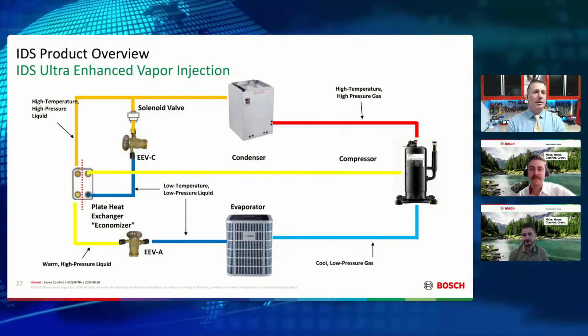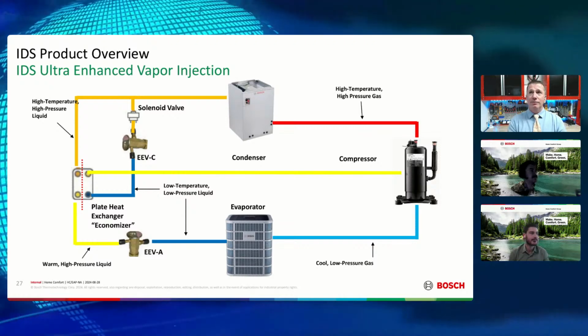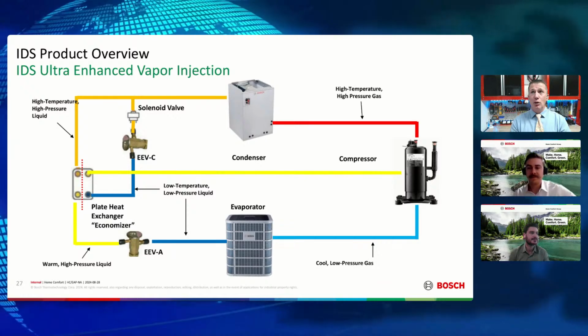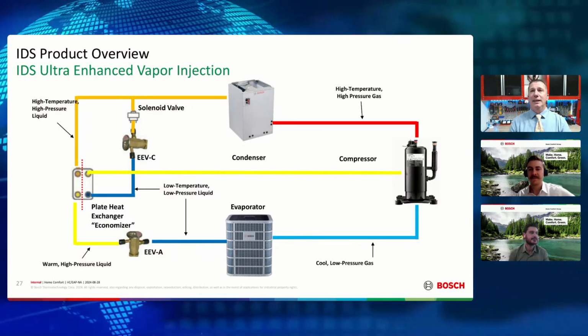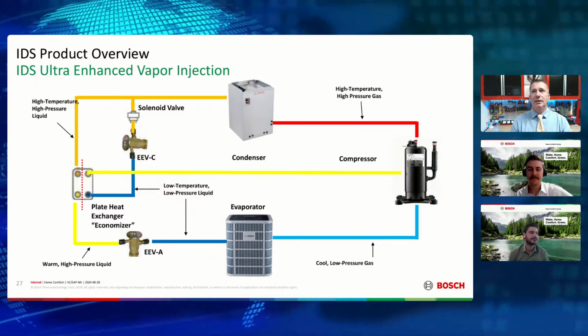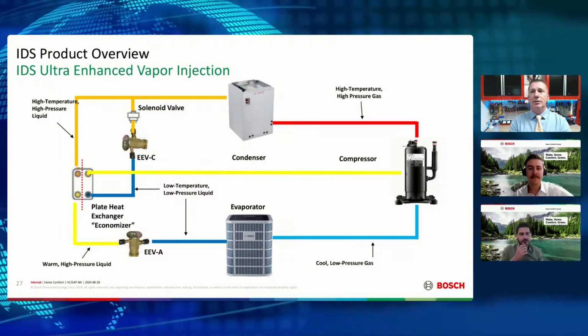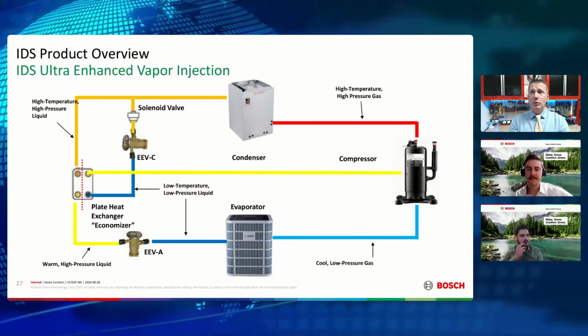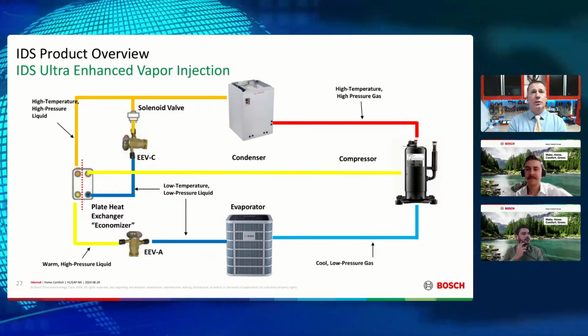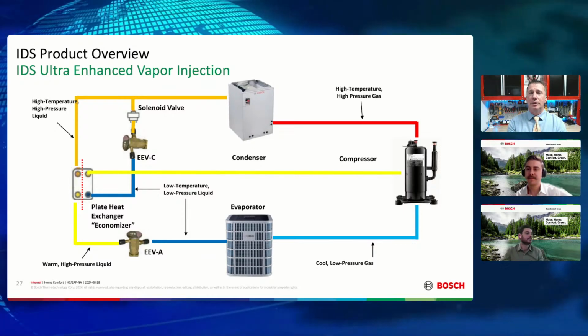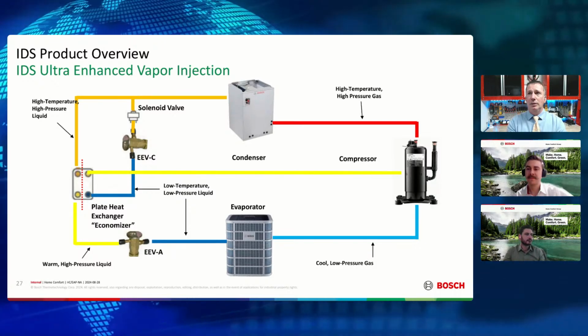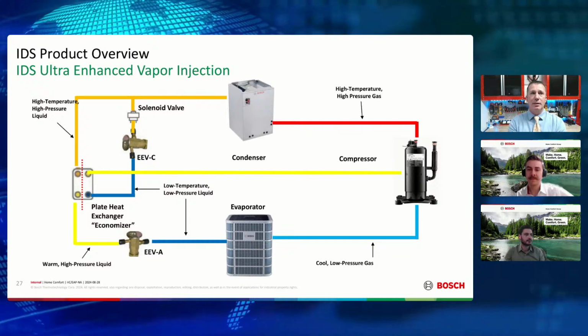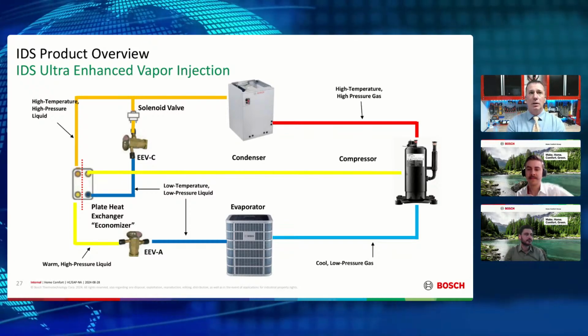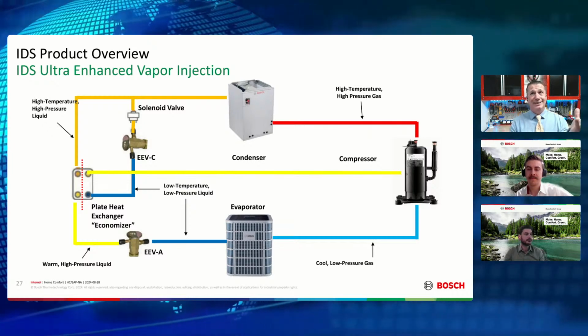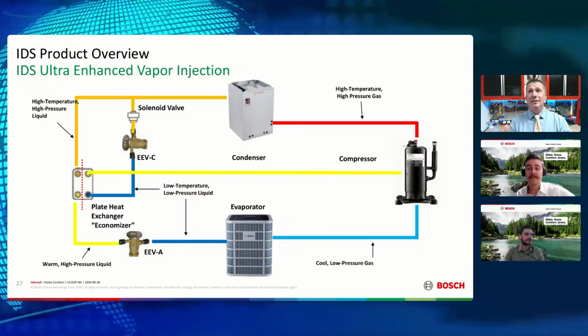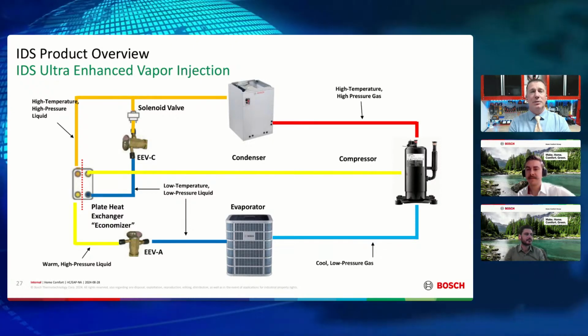Exactly. That's one of the biggest misperceptions when we talk about airflow. People say, 'Oh, those variable speed motors, those ECMs, they'll overcome some static pressure.' No, they don't. There's always a negative benefit. And the same way with our inverters, there's always a negative benefit. So it's going to be extremely important to understand the similarities and differences of these new pieces of equipment so that we're doing the proper installation. It's not a unbox, plug and go scenario, which some of our contractors have utilized in the past. We have to spend a tad bit more time on setup. But when we do, now we've got customization, and we can really do some amazing things with this very advanced piece of technology.